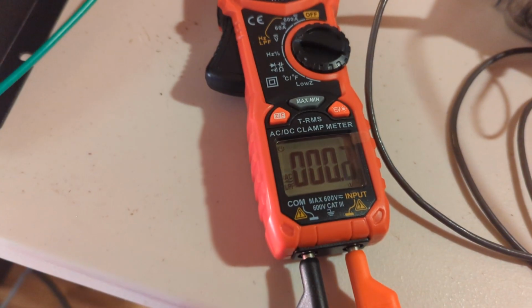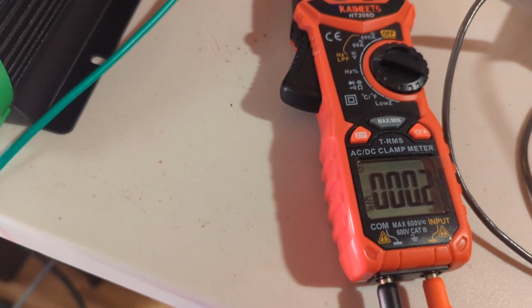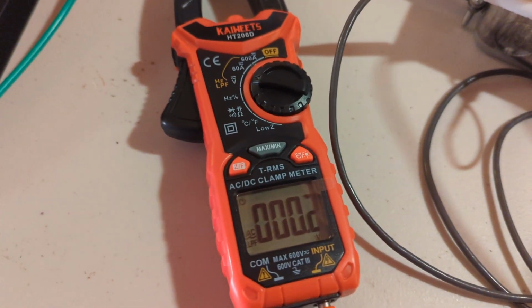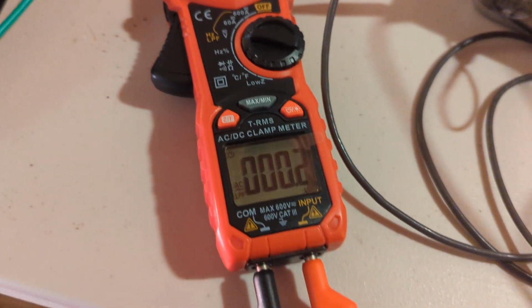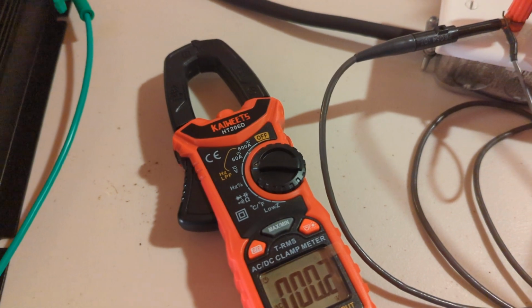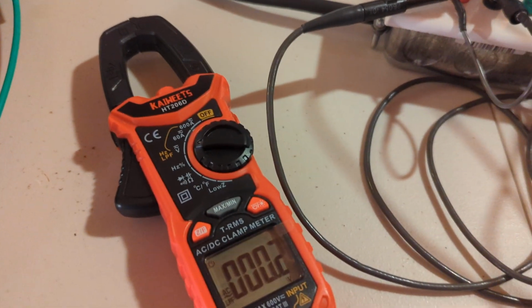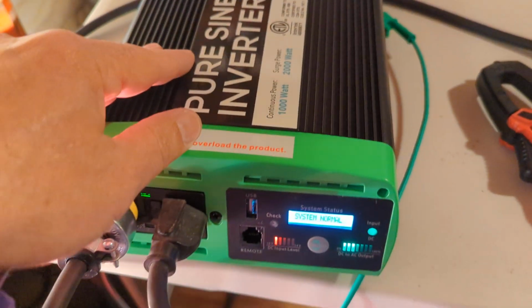So this is telling me that the neutral and ground are bonded. Once everything's powered off, I will take some resistance measurements to kind of verify that. But yeah, this is already a much better inverter than the other one.